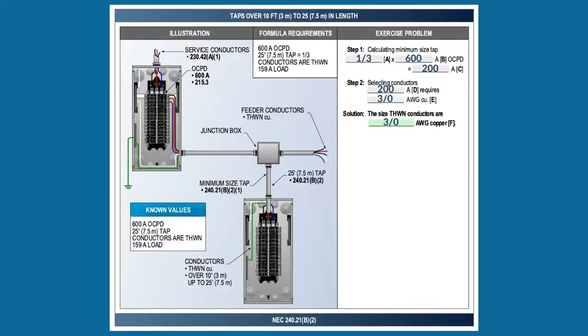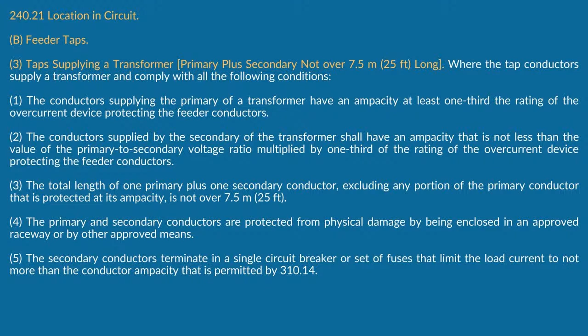Now, let's look. Here's where I deal with taps that have a transformer inside that tap. And if you look at the B31, it says to take it at what? 1/3. Okay. And then if I look at B2, it says the conductor supplied by the secondary. Okay, the primary is a third, secondary. It says shall have an ampacity not less than the value of the primary to secondary voltage ratio that's multiplied by what? A third. Okay, so as I said earlier, everything else is taken at a third, but if I have a transformer in the tap, I've got to get the ratio of the transformer plus take it at a third, and the primary's taken at a third. Okay, wow. So here's an illustration.